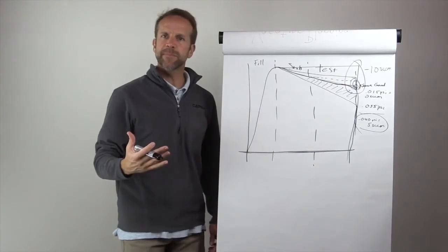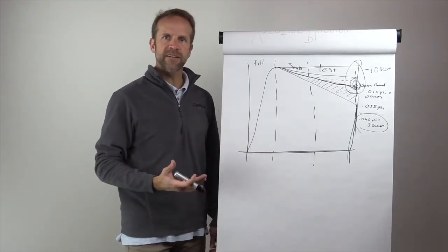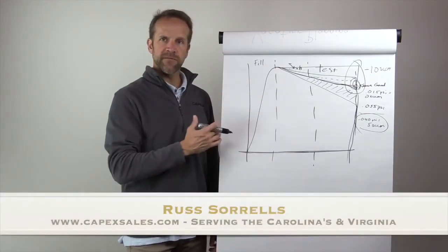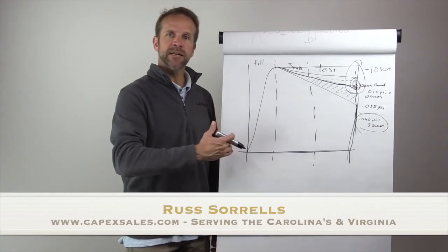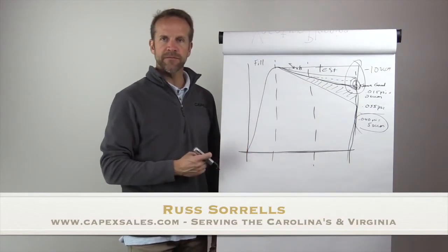So that's something to keep in mind with pressure decay leak testing. Why are you getting negative numbers? This is the reason for the negative numbers: the part you are testing after the calibration is testing better than the part you calibrated to.